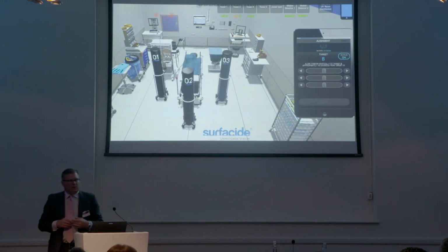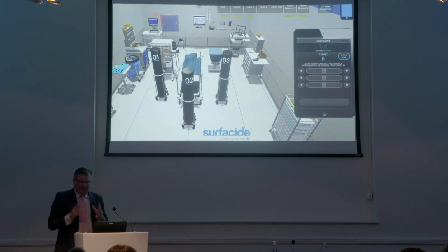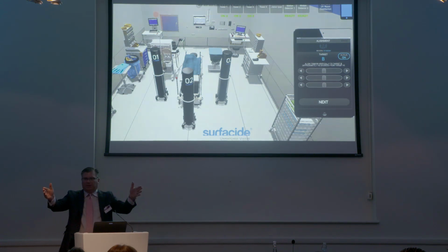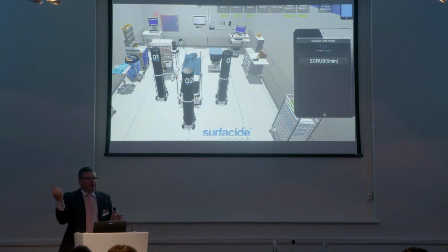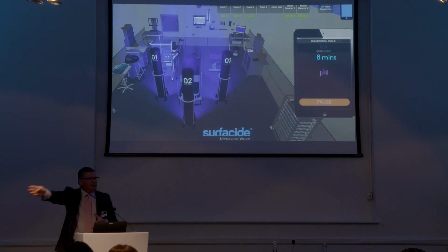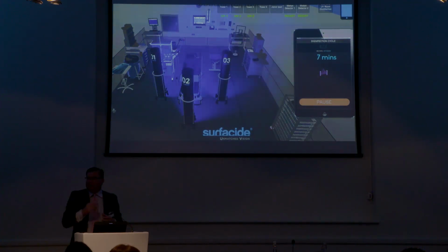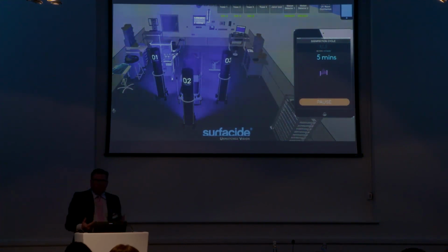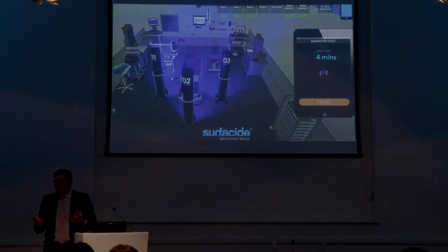I mentioned what we call the scrub cycle, which is a contained or a focused disinfection. So we utilize the onboard laser mapping by choosing goalposts, if you will, a right and a left margin. And rather than rotating in 360 degrees, all 3 emitters for a period of about 7 minutes are just going to oscillate back and forth to those user-selected start and end points. This is the mode we would use in a multi-bedded bay or in a Burns or in a post-op PACU area.